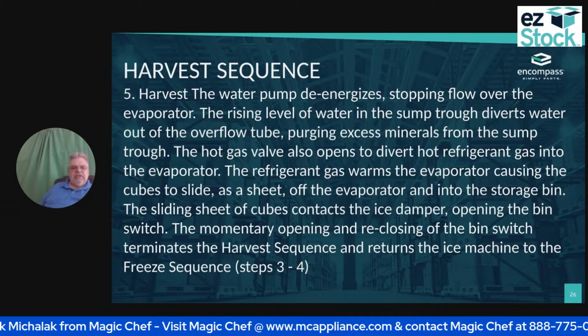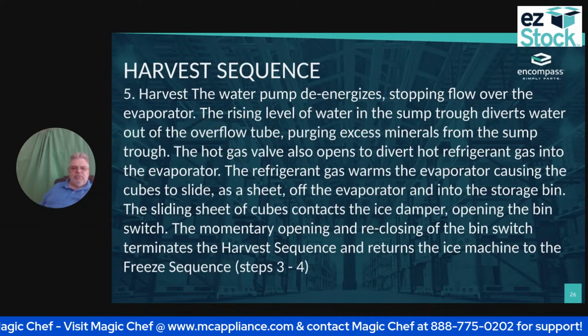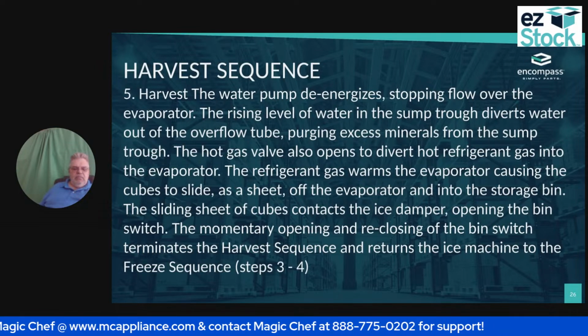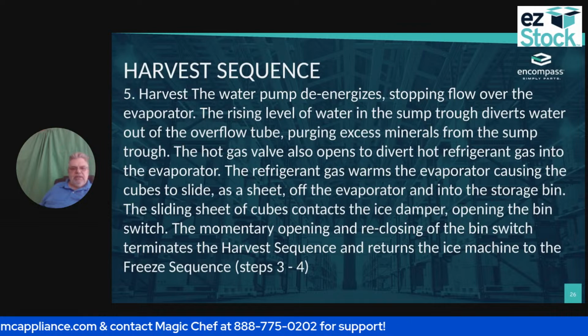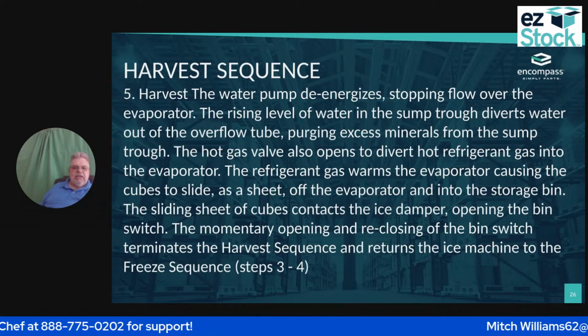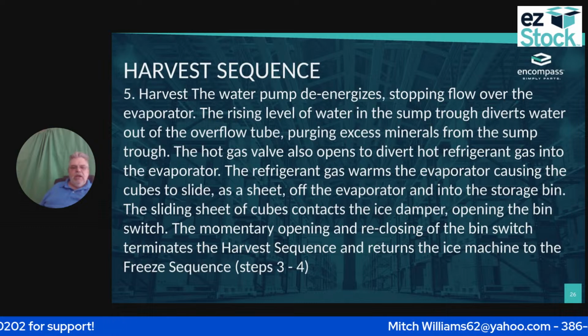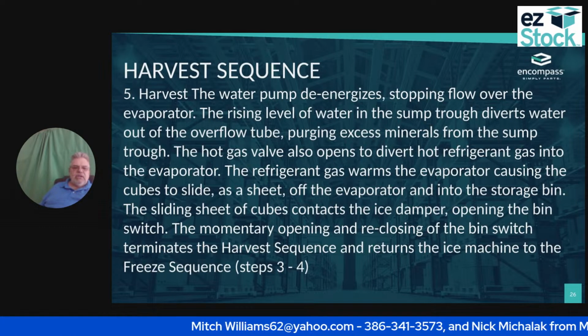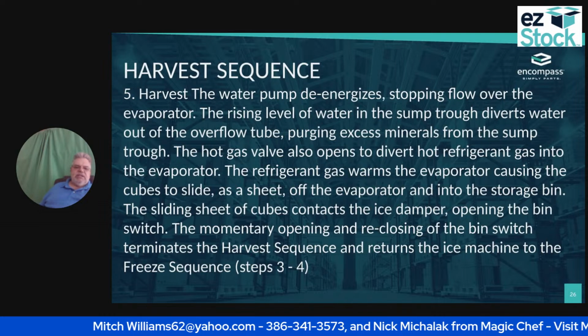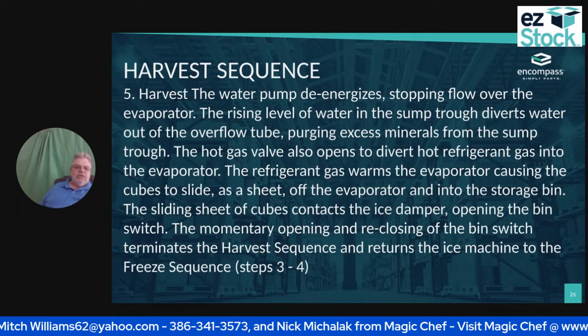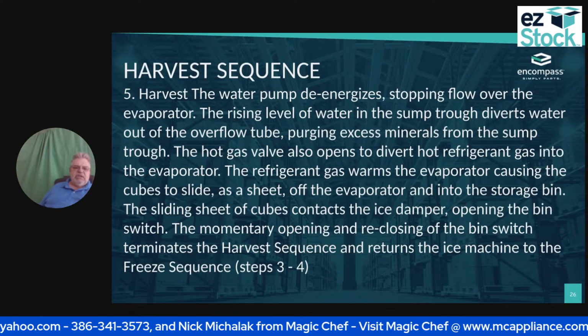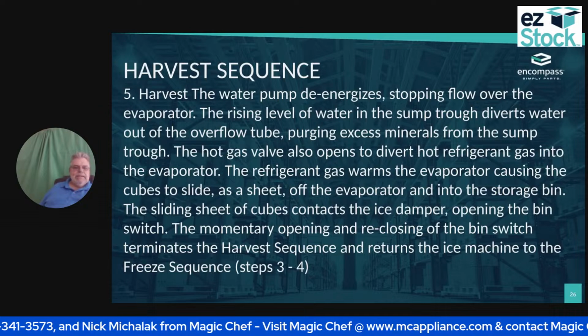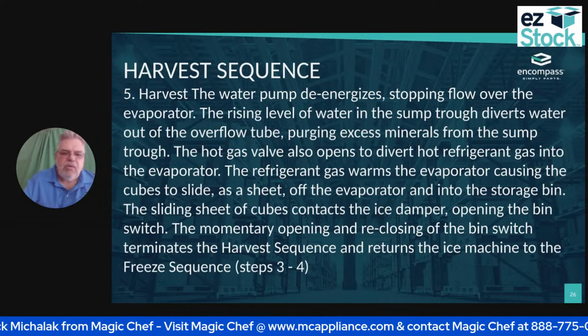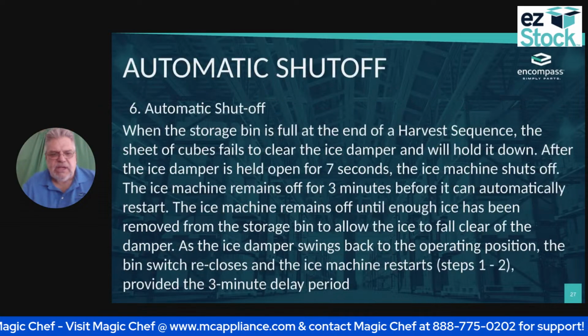But that's usually when I'm going to have to adjust my switch to make that happen properly. Okay, the sliding sheet of ice cubes contacts the ice damper. It opens the bin switch. The momentary opening and reclosing of the bin switch terminates that harvest cycle, and it returns the ice machine to the freeze sequence. Okay, so we have now been through a harvest cycle.